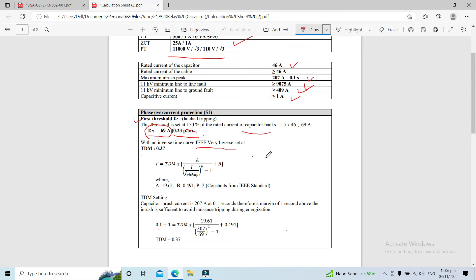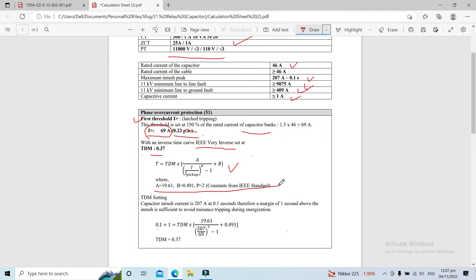After solving the time-dial multiplier equation, we derive a value of 0.37. This is the equation for this particular curve, and we have the constants from the IEEE standard — the values of A, B, and P.